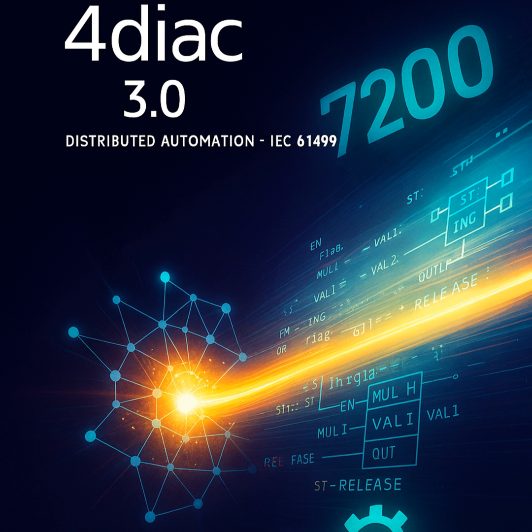Okay, VAR_IN_OUT, let's pause there. For someone maybe not deep in the weeds of 61131-3, why is that specific variable type important? What's the practical benefit? Performance and memory efficiency, big time. VAR_IN_OUT is about passing data by reference, not by value. Meaning you don't copy the data. Right. Imagine you have a large data structure, maybe an array with thousands of sensor readings. If you pass that by value into a function block, the system has to copy that entire chunk of memory. That takes time and uses up potentially scarce memory.